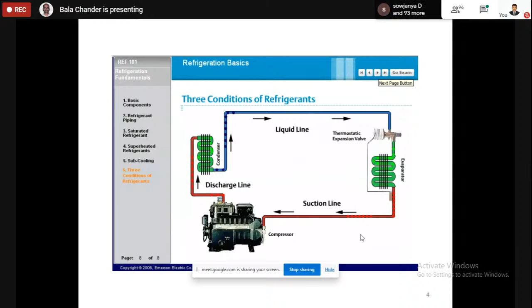Initially at the compressor inlet, you will have something like 0.8 bar. The pressure is being raised to 7.8 bar - so the pressure is being raised. You can see the temperature is around 2 degrees centigrade at the inlet to the compressor, and around 60 degrees centigrade at the outlet temperature of the refrigerant.